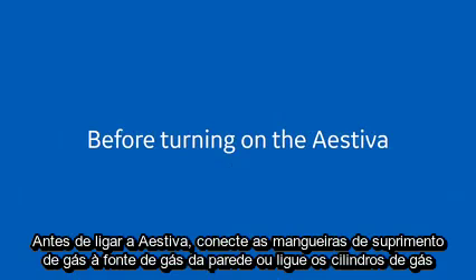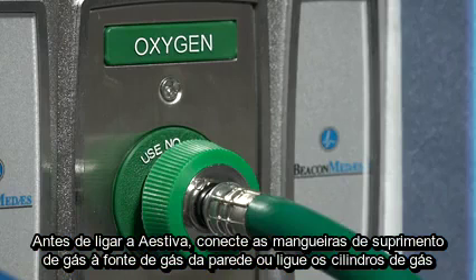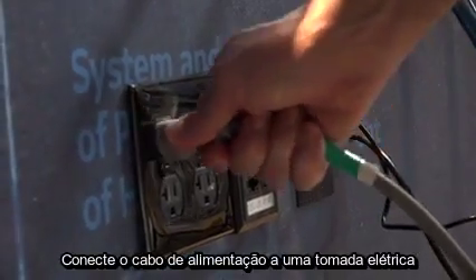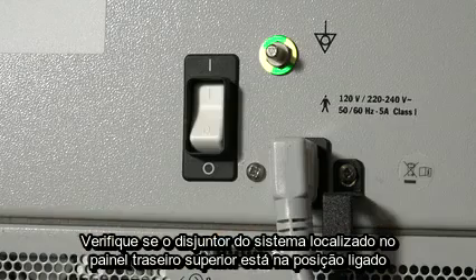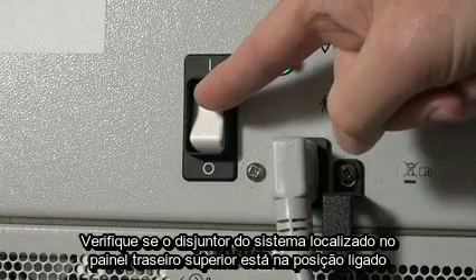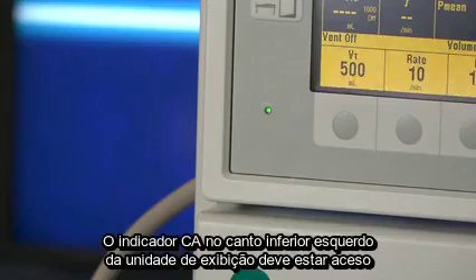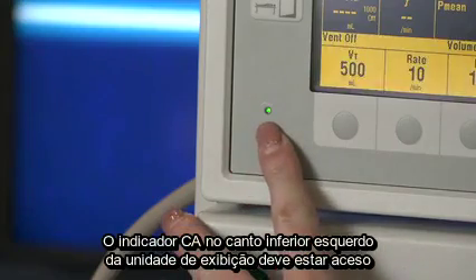Before you power on the Aestiva, connect the gas supply hoses to the wall gas source or turn on the gas cylinders. Plug the power cord into an electrical outlet. Make sure the system circuit breaker located on the upper back panel is in the on position. The AC indicator on the bottom left corner of the display unit should be on.